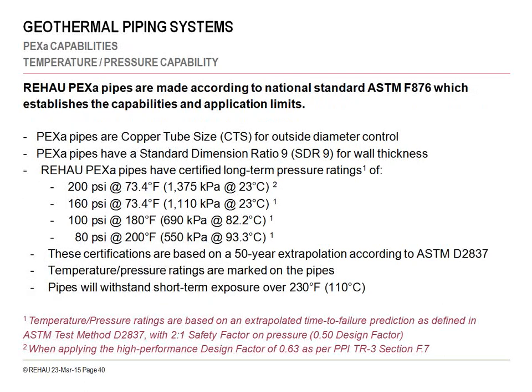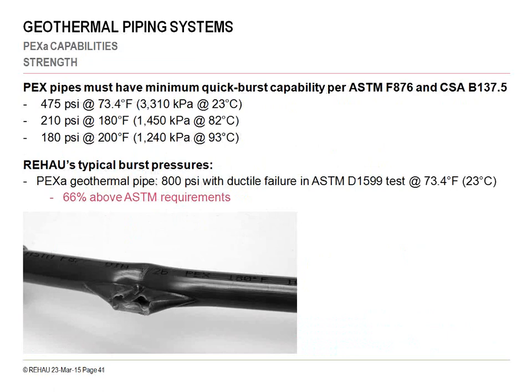So, you know, here are some of the temperature and pressure capabilities of the PEX-A pipes. And as I mentioned, 200 psi at 73 degrees Fahrenheit. And you can see we're actually having ratings all the way up to 200 degrees Fahrenheit at 80 psi. Some folks would say, well, you'd never see a geothermal system that would have those kind of temperatures. And that's true, but sometimes we see hybrid systems that could be integrated in with, say, a solar thermal system, which would be providing higher temperatures to the hybrid system.